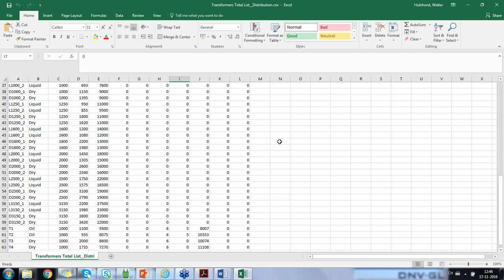And then I think the one should be in, well, it doesn't matter how you calculate it, but both of those transformers, or you can add one transformer with a YY delta configuration. So make it 3 winding transformers. But very often you will see that people buy two transformers having the same output, but only one is in YY and the other one is in Y delta. And then you can compensate the 5th and 7th harmonics, so you're getting only the 11th and 13th harmonics.